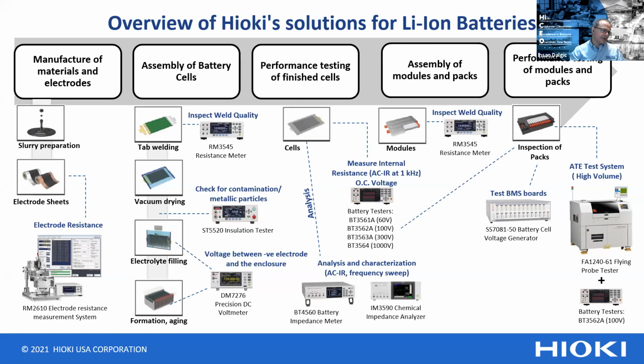This is a very specific test and measurement system, the RM2610. It measures the electrode resistance of the electrode sheets. Then when we get to the assembly of the battery cells, for instance, inspection of the welding and checking for metal particles, etc., Hioki also has test solutions for that. These instruments tend to also be used in different types of situations. For instance, the resistance meter that can measure in the ohm or nano ohm resistance range.